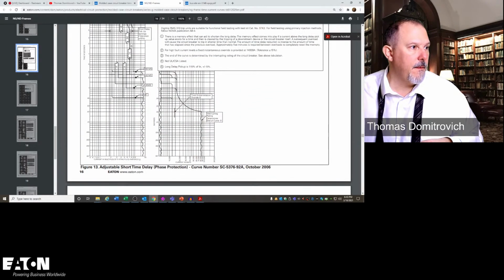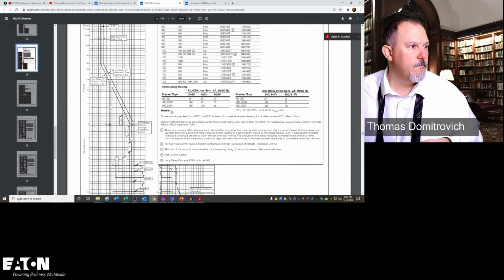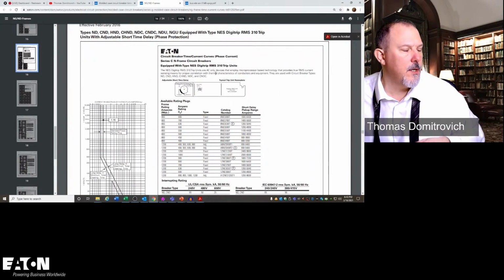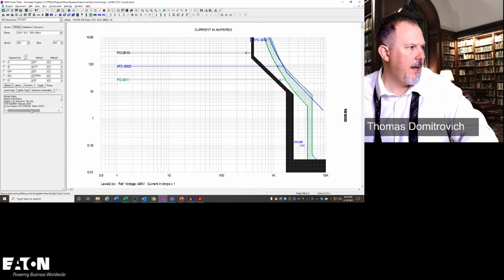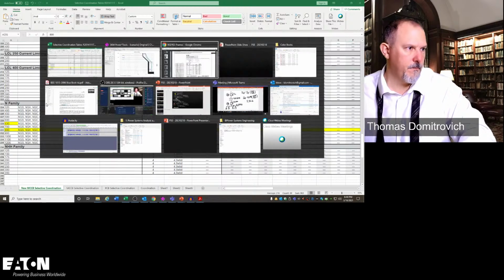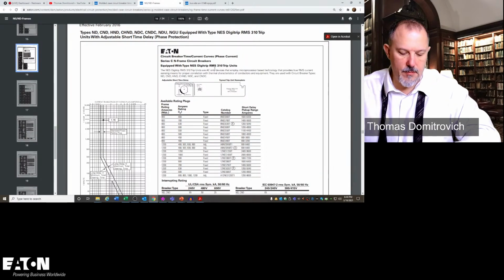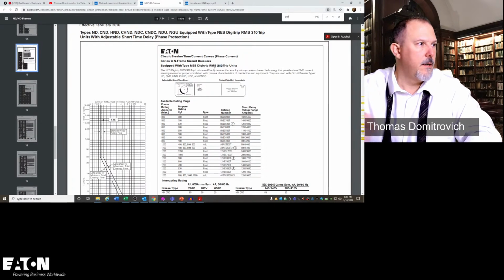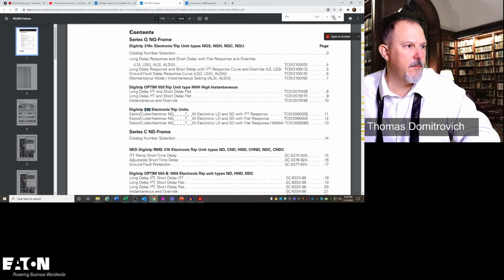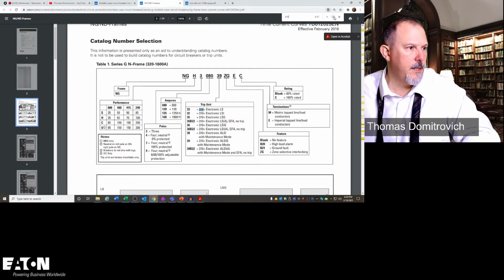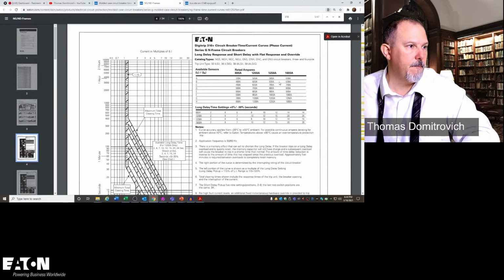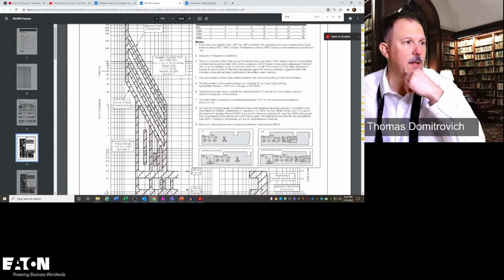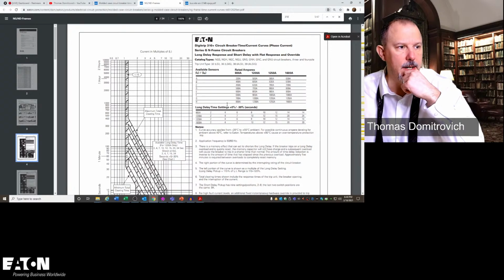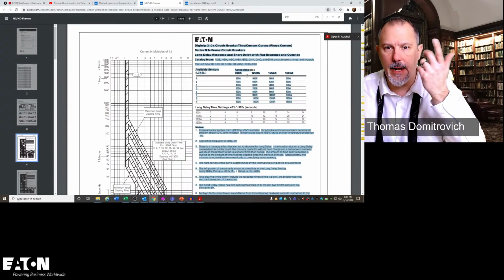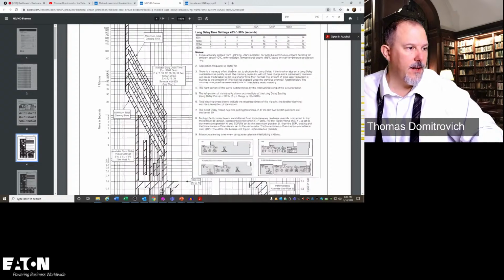And these are my instantaneous. Let me just look at my trip unit. Ooh, what trip unit did I have? Let me look at my SKM. I had a 310 plus trip unit. So 310 plus, 310. There's a 310. I'm just going to see if there's a 310 plus. There's my 310 plus, and there's my 800. So there's my frame rating, 800 amps. Whoa, my 800 amp frame.